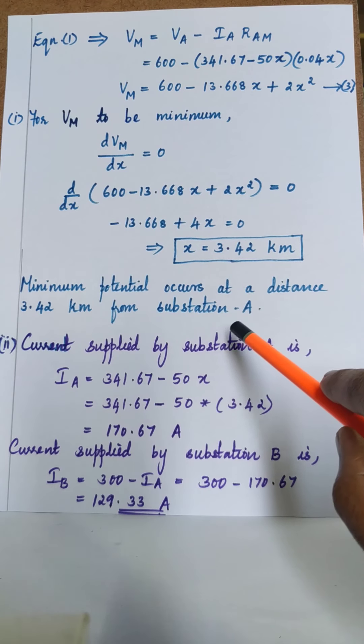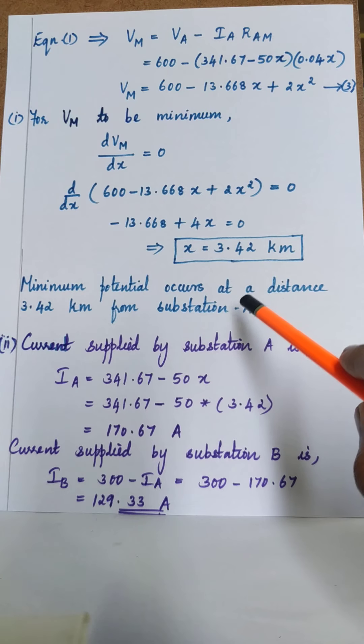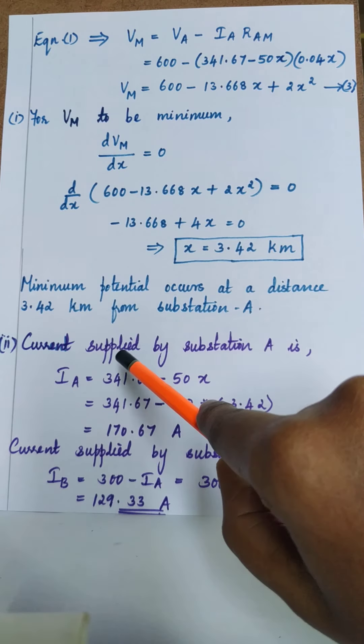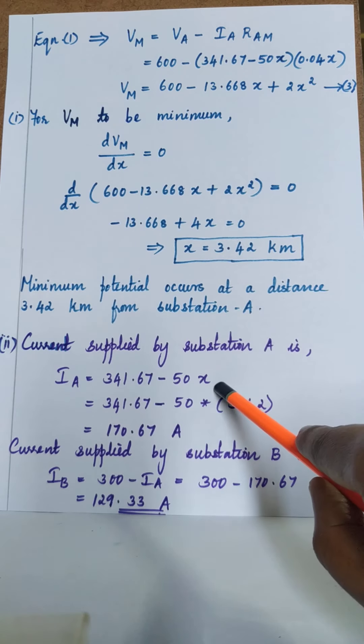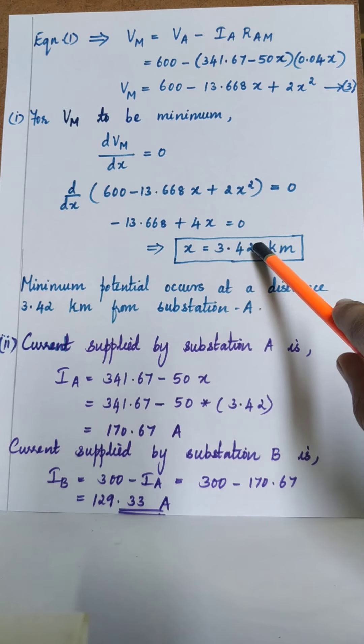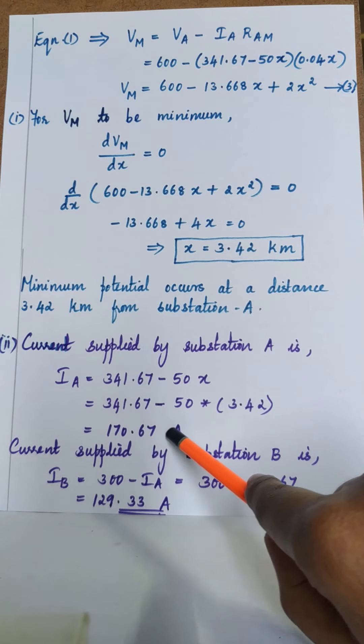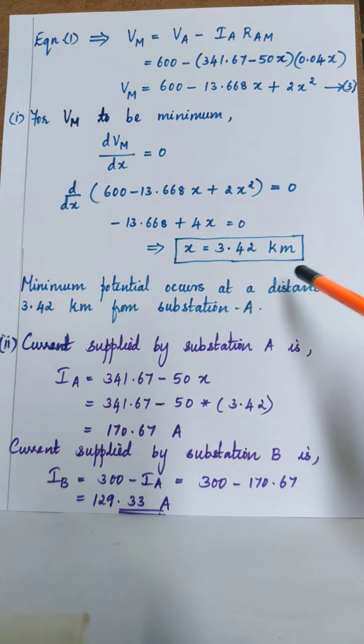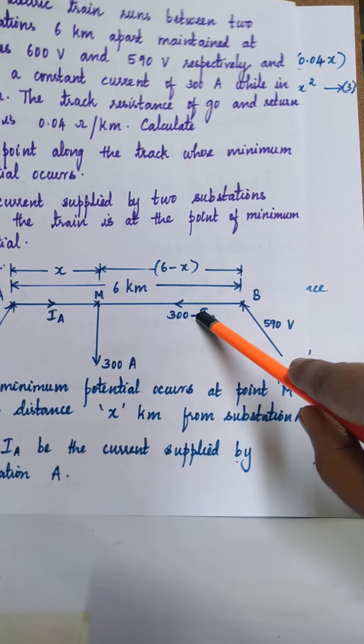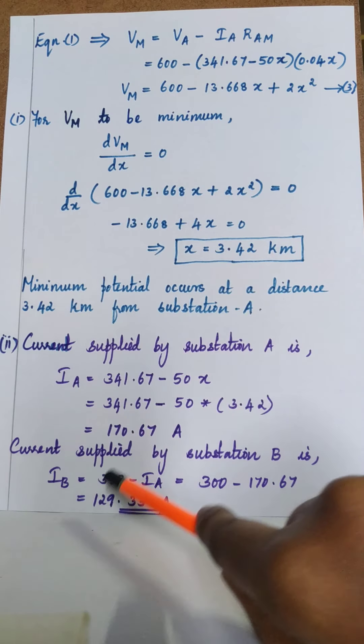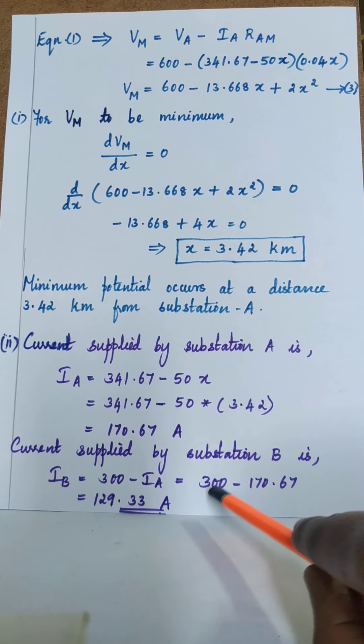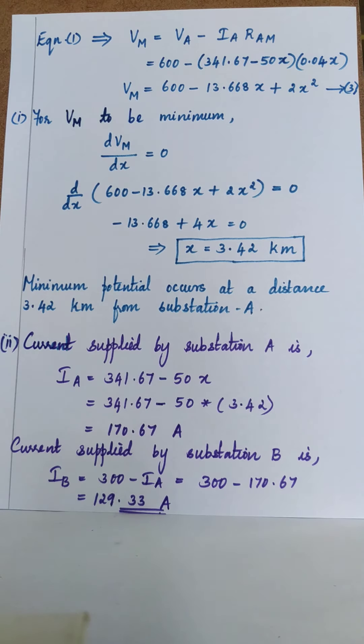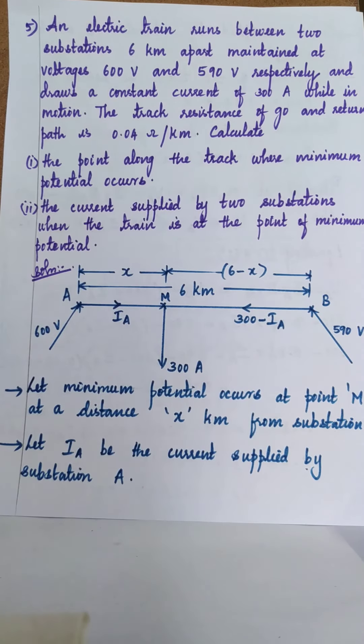For part two, we find the current supplied by both substations at the point of minimum potential. We already have Ia = 341.67 minus 50x. Substituting x = 3.42, the current supplied by substation A is Ia = 170.67 amperes. The current supplied by substation B is Ib = 300 minus Ia = 300 minus 170.67, which gives approximately 129.33 amperes.